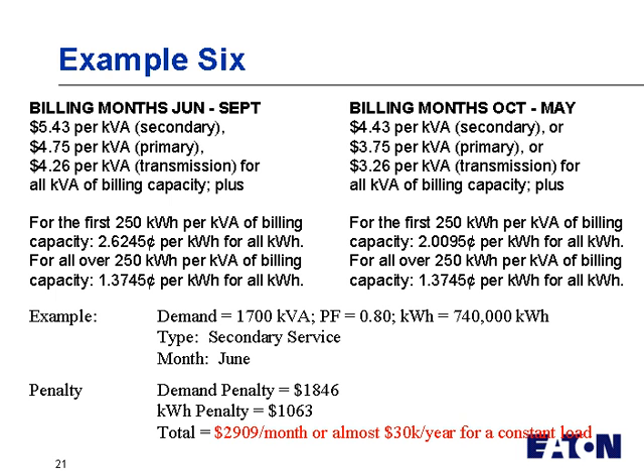And as it turns out down below, you can see just for this 1 month that we show as an example, the demand penalty is $1,846, and most people would be able to calculate that based on the kVA versus the kilowatts. But the hidden charge in this case, I think, is really the kilowatt hour penalty, and that's almost as substantial, in some cases even more. I could show you other examples.